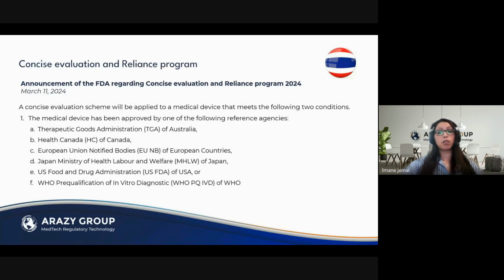Another announcement was also published last month regarding an amendment in the evaluation scheme for the concise evaluation route. It stated that now there are two conditions that should be fulfilled for the concise evaluation route. First, that the medical device has been approved by one of the following reference agencies: TGA, Health Canada, European Union Notified Body, Japan Ministry of Health, Labor and Welfare, FDA, and the WHO for prequalified IVD. This is the first condition for the concise evaluation route.